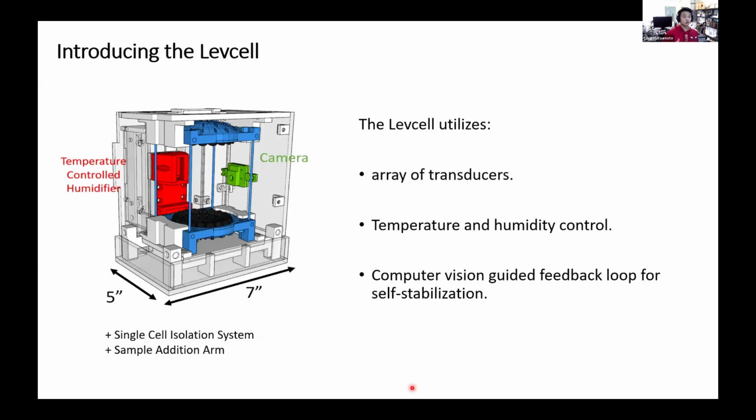That introduces the LevCell, a fully automated containerless sample processing system, which utilizes acoustic levitation and was developed in the Gao lab. So this is the main body of the LevCell. It's comprised of 3 main components. First, we have our transducer base in blue.